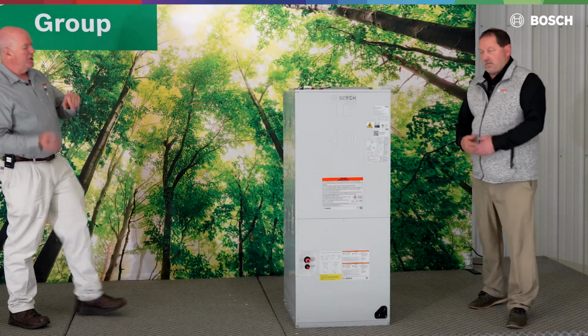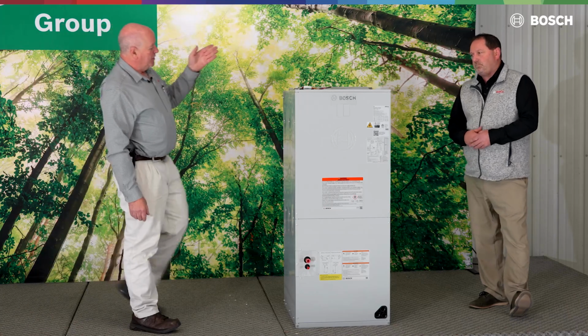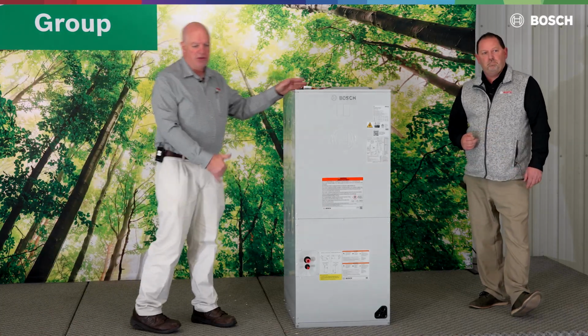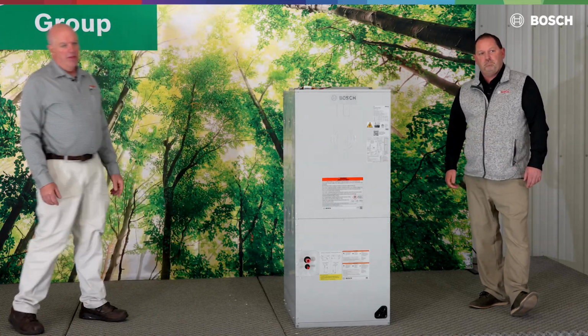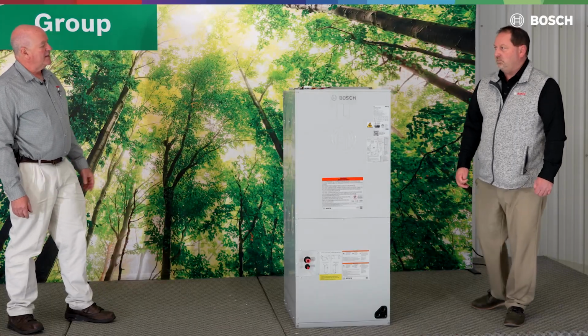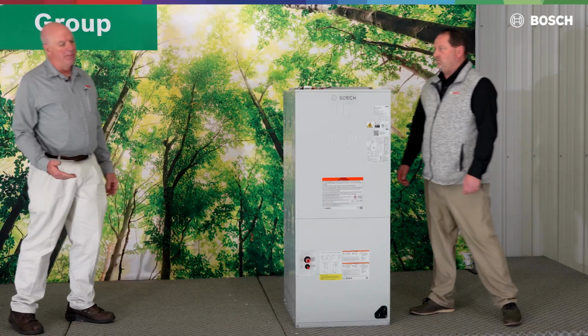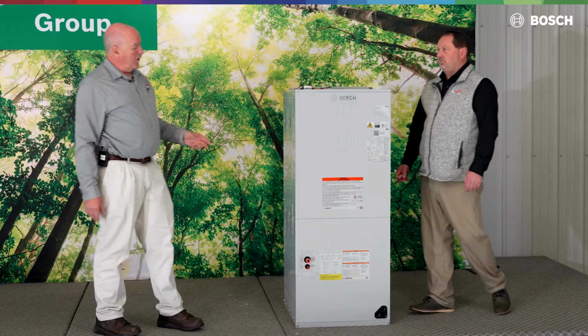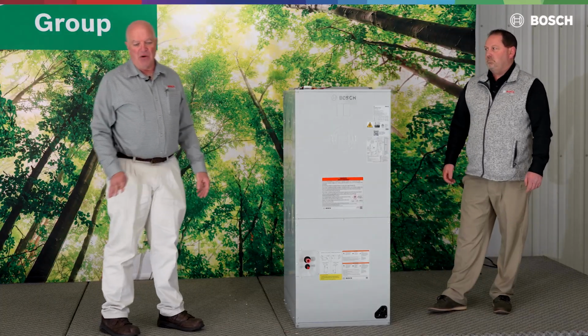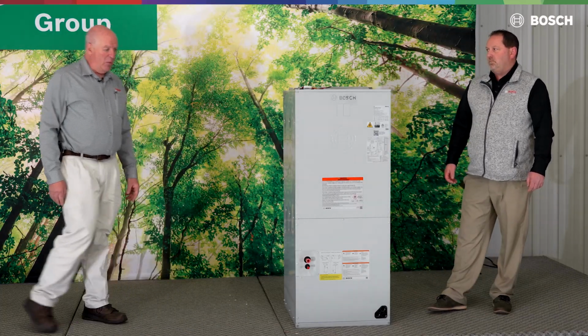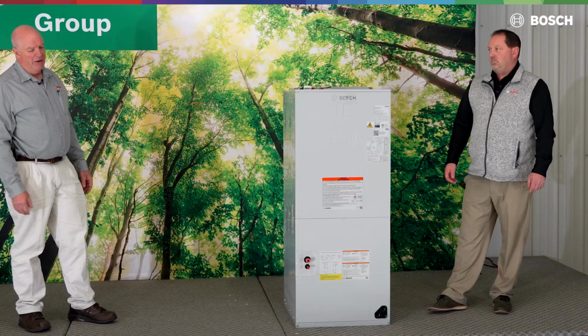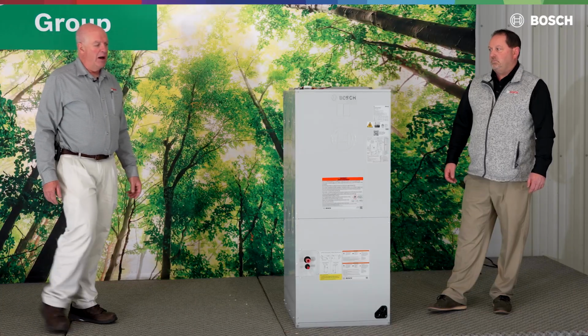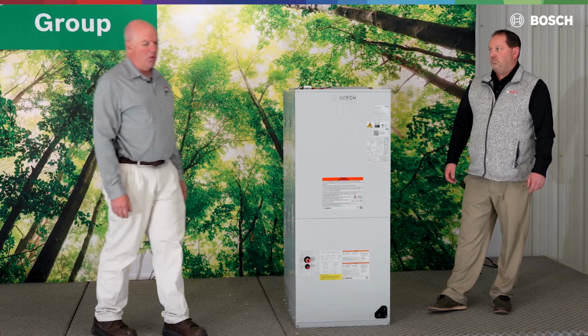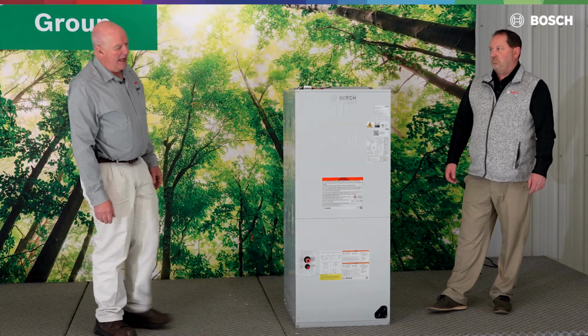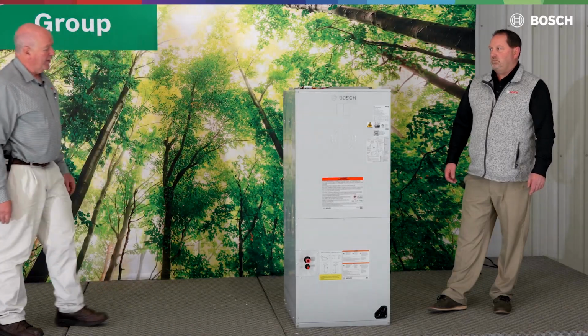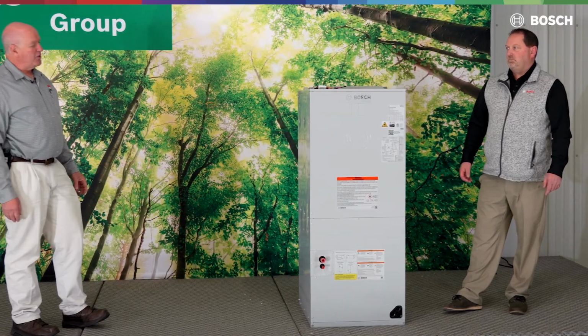And that information is brought back through the cloud to the air handler, and it chooses its temperature with the compressor section. The third style is going to be one that's not necessarily a Bosch air handler, maybe not a Bosch coil. At that point, we have 4 conductor wire standard to all the IDs we've had before. We'd have our blue wire, which would be for our reversing valve. We have our brown wire, which is common. We have our white wire for electric heat. And we have our yellow wire for the compressor section. So that's what we have going on.